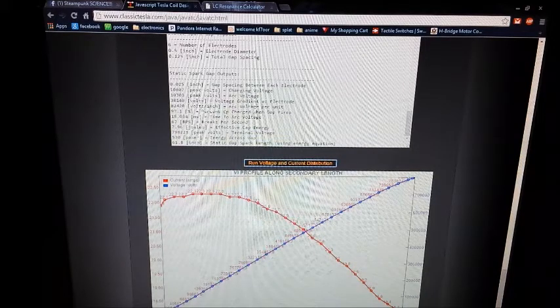At my output, my current, about 18.1 amps, and the very high voltage is about 790-something thousand volts, so about 800,000 volts there. If I were to tap it off at any of these points, it tells me the voltage and current per that specific point. Again, the maximum is 22.3 amps on the primary.